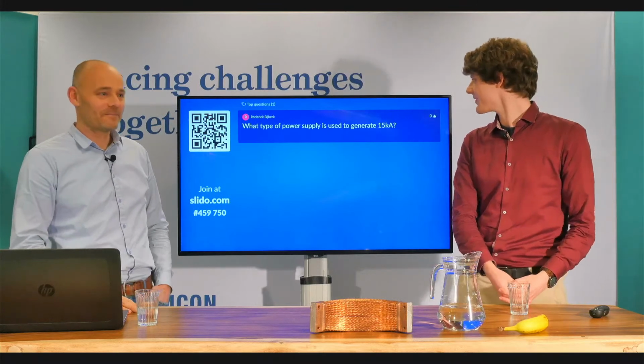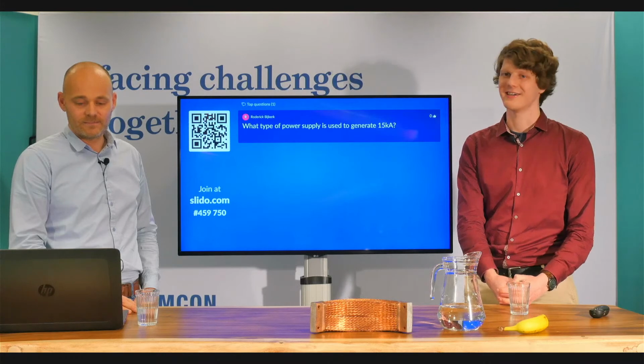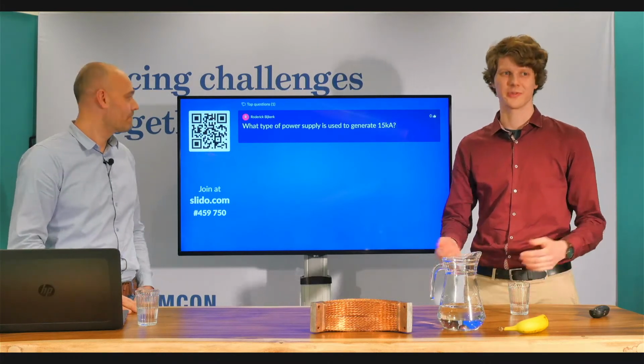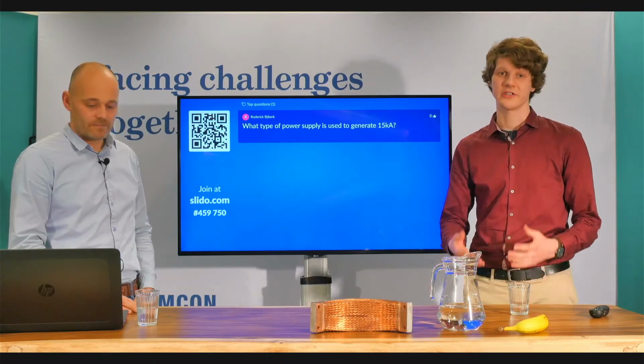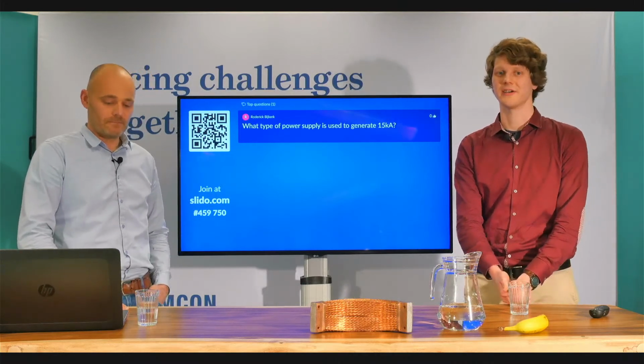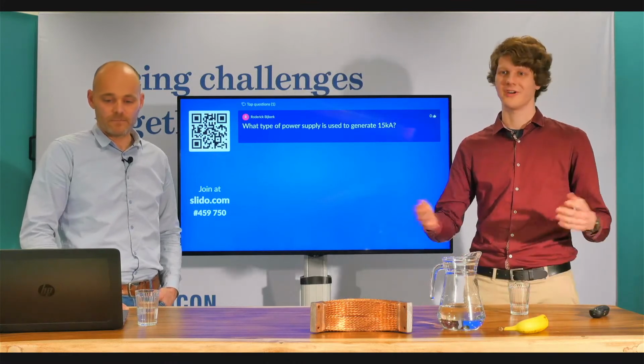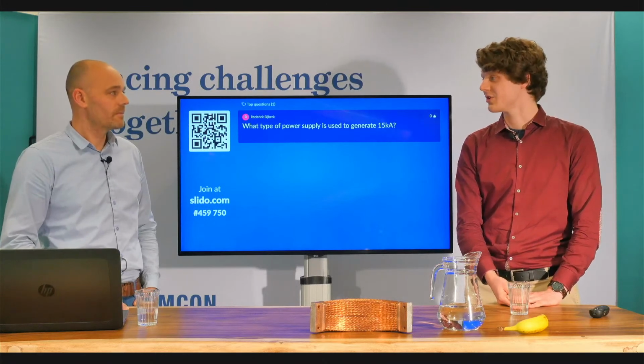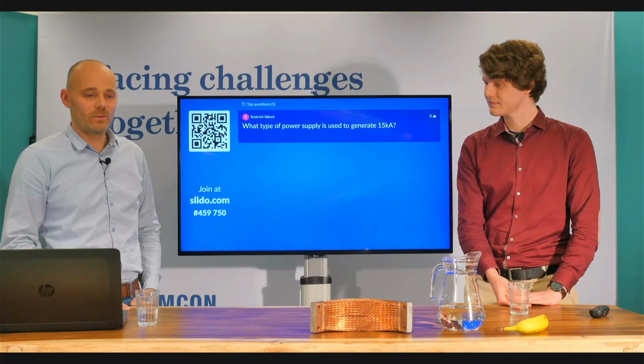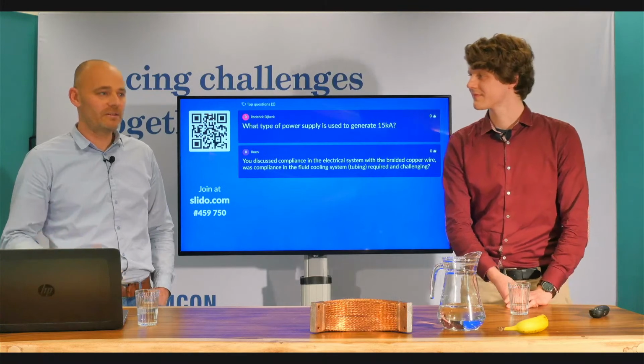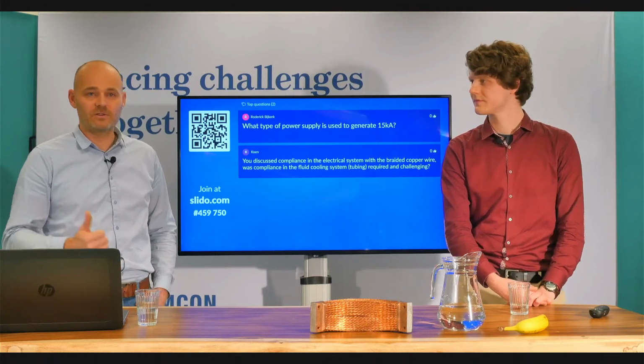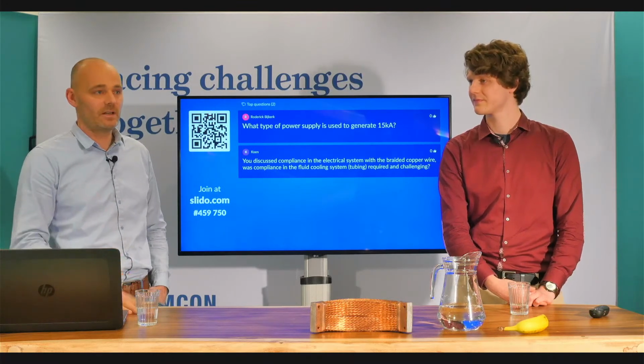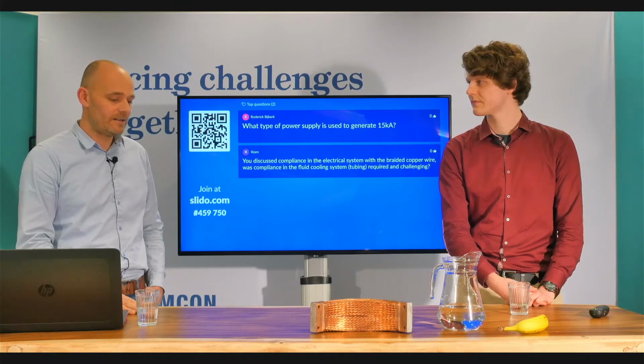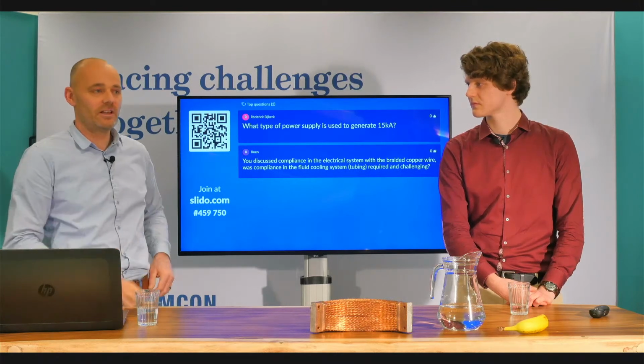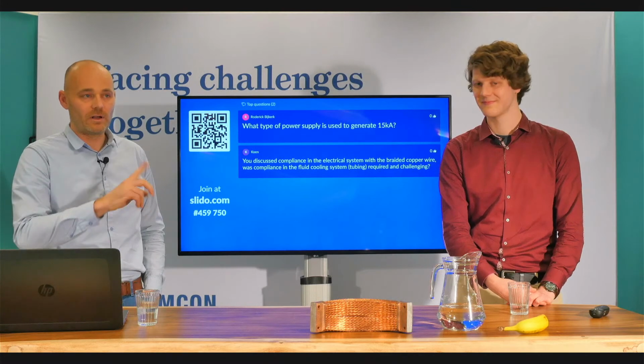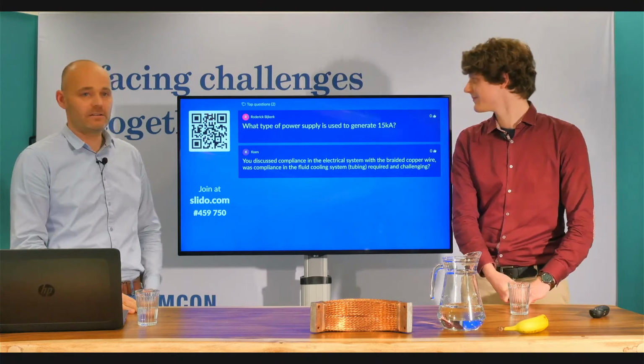So the next question is what type of power supply is used to generate 15 kiloampere? Surprisingly, this is a rather standard component. When we were looking into all the options, it happens that in the power industry, high power electrical components like these are made more often than you would think. So we didn't have to go all out with a supplier and design something entirely new. Yeah, I believe it's just standard. What is good to mention is that you also need to connect it to the power grid in the building, and for that we had to change a transformer outside the building. We had to increase the power supply for the whole company locally, and there are two wrist-size cables running inside the building to power our full setup. That needs to be taken into account, but other than that, it's a normal power supply.